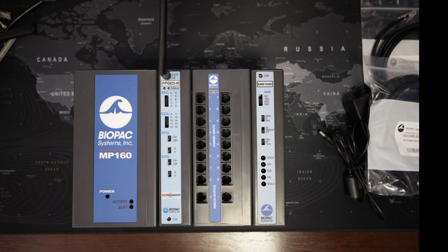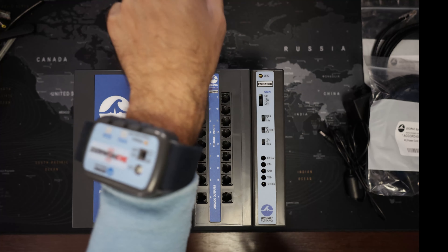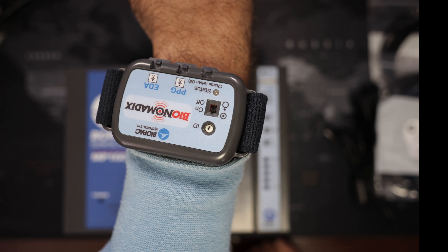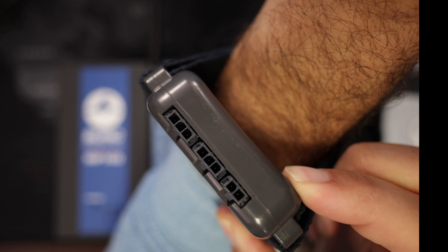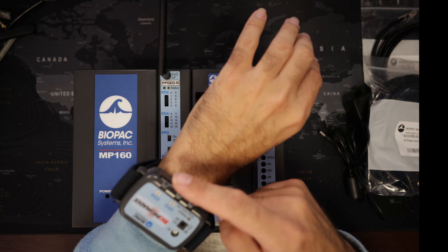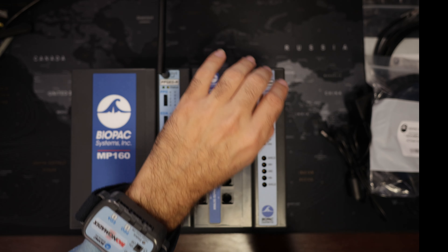I'll put it on. Now it's transmitting to the main unit. You can see here the connectors — the same BioNomadix-style connectors that we use for the smart amplifiers. So electrodes connect here. For EDA they would go to our electrodes, or if we're using a pulse transducer, we connect from the pulse transducer, to be worn on the finger of the participant. The same principle applies for all the other wireless modules.